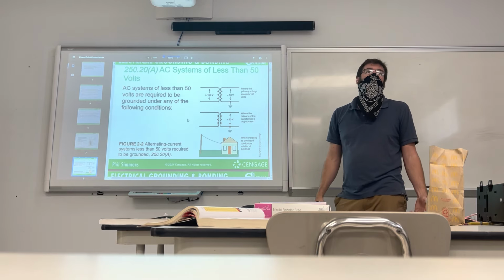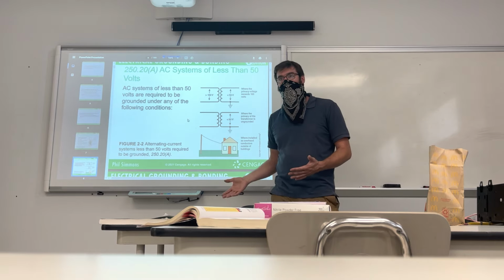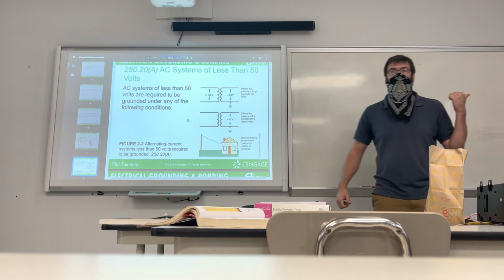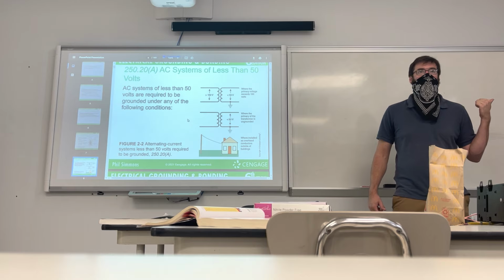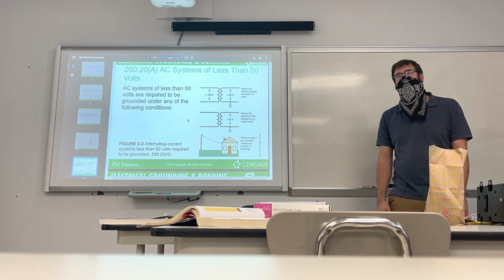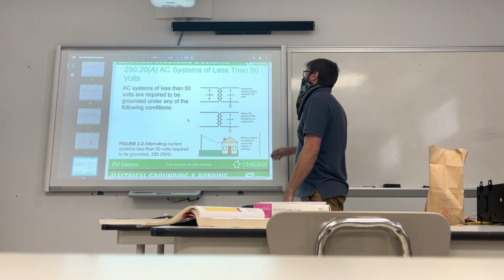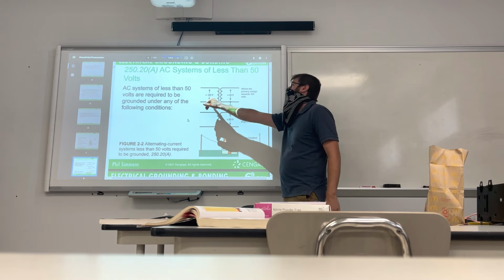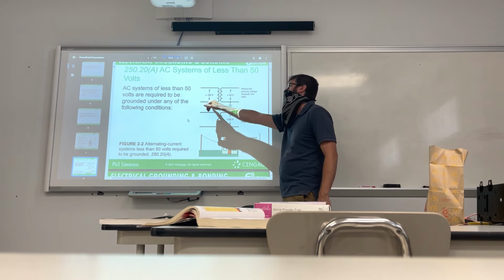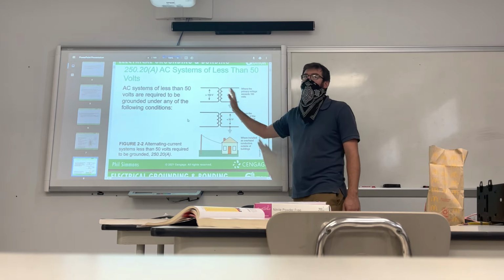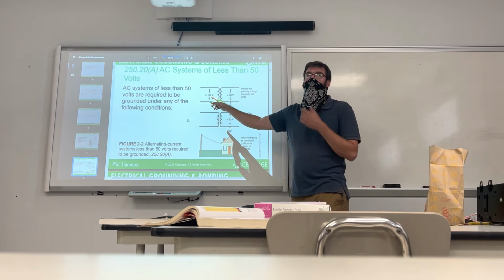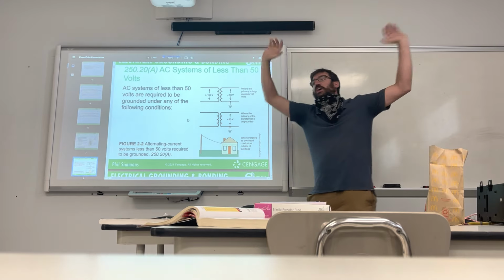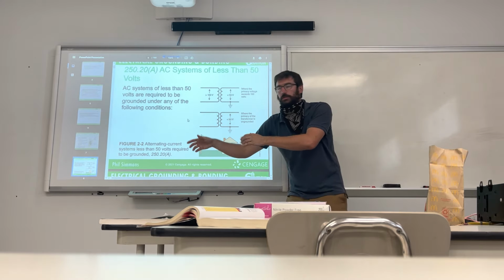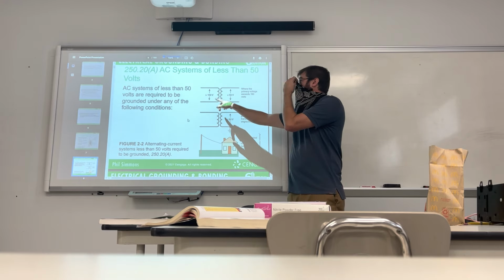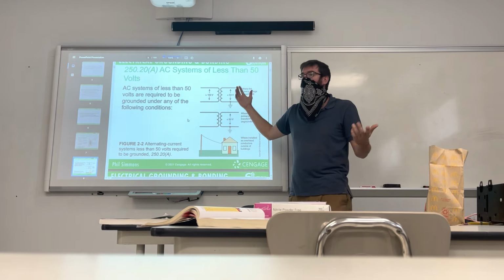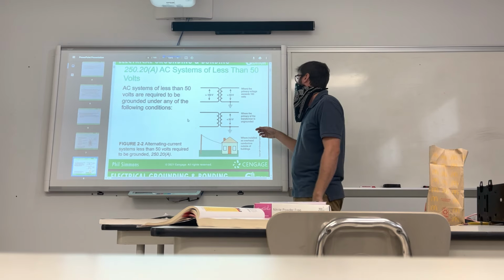But as I just proved to you, if electricity is not dangerous below 50 volts, then who wants to go out and grab the battery in my truck? Anybody want to join me? No? Oh, that can hurt you too? Okay, so I just proved that to be wrong. So yeah, it does have to be grounded if the primary is 150 volts or higher. And that just means it's stepping down, and that could be anything. That could be 120, it could be 240. As long as you have the right transformer, you can step down any high voltage to any lower voltage, okay? But just note that you have to ground it if that initial voltage is 150 or more. But once again, I will ground it regardless.